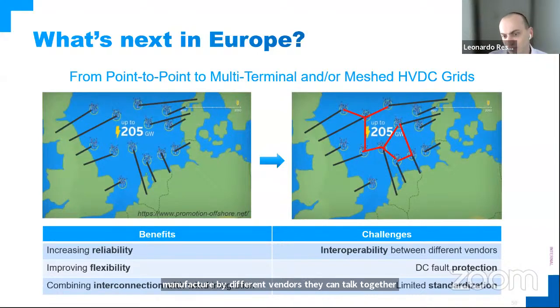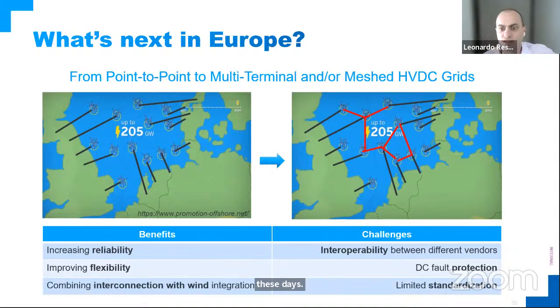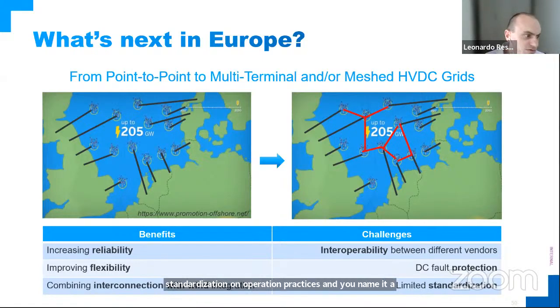Another well-known challenge for multi-terminal mesh DC grids is DC fault protection. We can't use circuit breakers like in the AC world; for DC fault protection we need special DC circuit breakers, which is another very active area of research and development. Linked to interoperability is standardization: we need standardization in functional specification, in equipment design, in operation practices, and more.